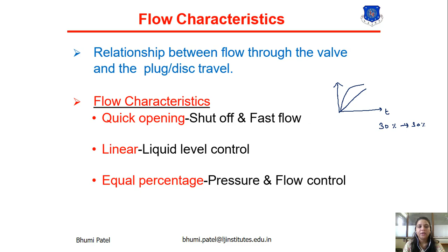Now what is the equal percentage? The change of the valve depends upon the percentage ratio. An example is pressure and flow control. If we apply 30% flow in the inflow, we get the same percentage in the output flow rate. So this type of flow characteristic is known as the equal percentage. So we have mainly three types of flow characteristic: quick opening, linear and equal percentage.